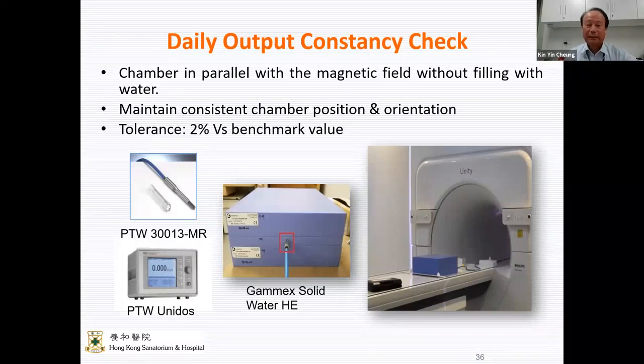And we also do a daily constancy check using a solid water phantom. Now for this phantom, because of the time limit, we take an easy way and put the phantom flat on top of the couch, so that we cannot put water into the insert to reduce the gap. So we just leave the chamber as it is, and mark the orientation of the chamber so that it is inserted in exactly the same orientation every time. So we try to minimize the inconsistency of the gap.